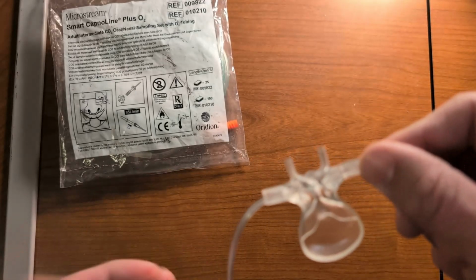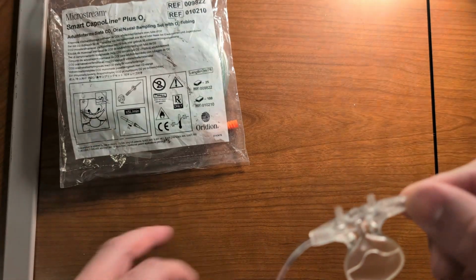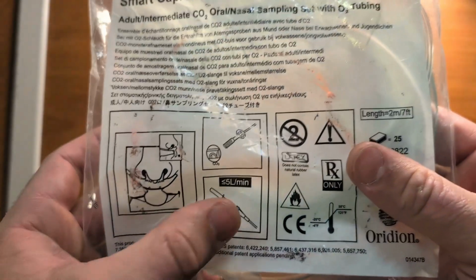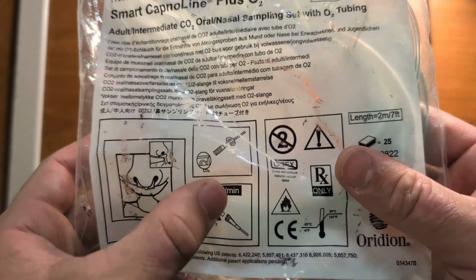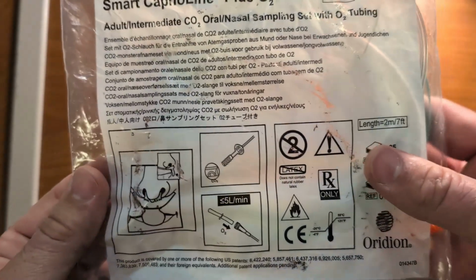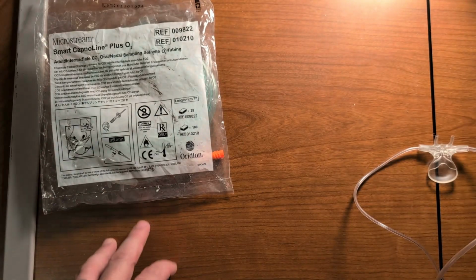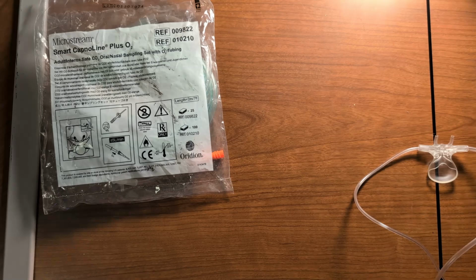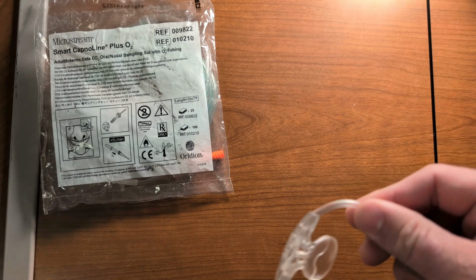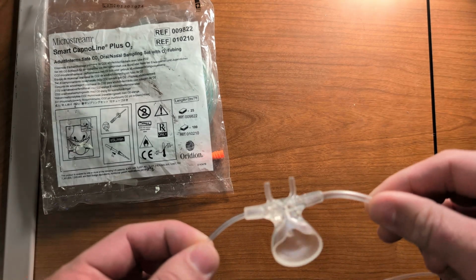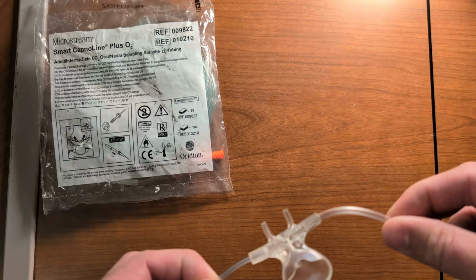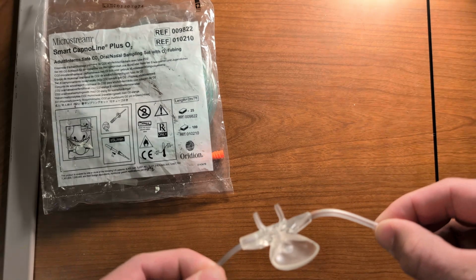All right, so our regulators go from 4 to 6 liters. So our limit practically is going to be 4 liters per minute. There's one more notch up and we're going to be over this limit, and we're going to start having an affected end-tidal reading. Now, I tested this with oxygen. I didn't see an appreciable difference at 6 liters. Maybe 1 or 2 millimeters of mercury, not a whole lot, but just know that it is possible.